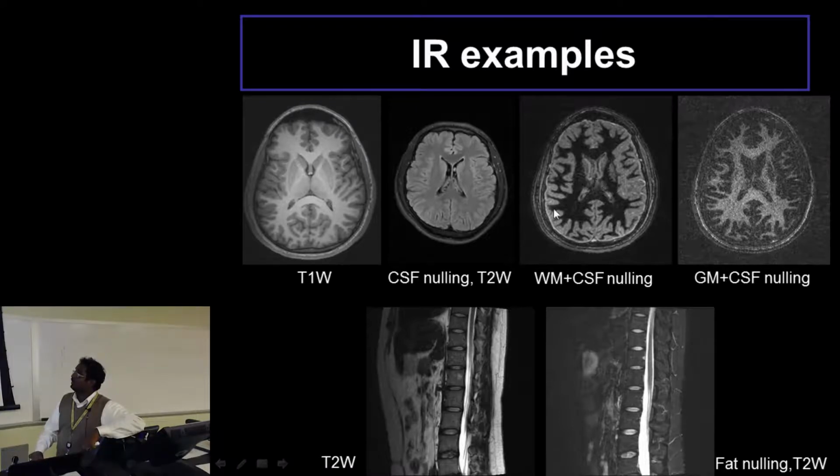You could also do dual tissue suppression. There you have two 180 degree pulses, 180 and then 180, and then the 90 degree pulse. You can write that equation. Under certain conditions you have to assume that TR is long, and it simplifies. If your TR is very short, it gets a little more complicated. But under simplified conditions you can derive the equation, and then derive what TI1 and TI2 should be if you have two inversions, to null two tissues.